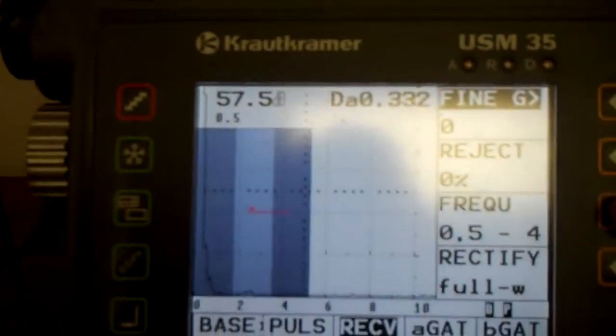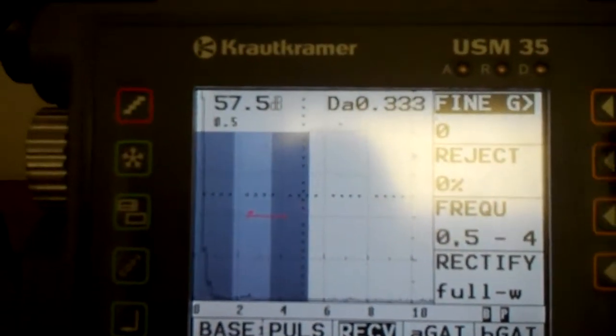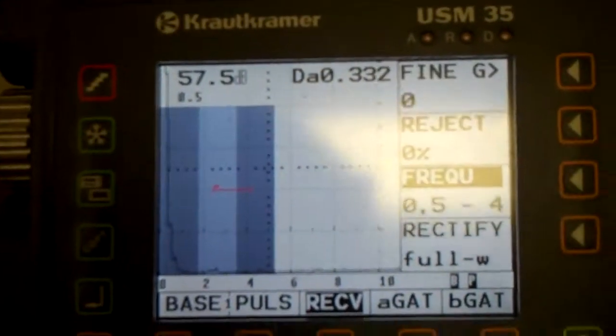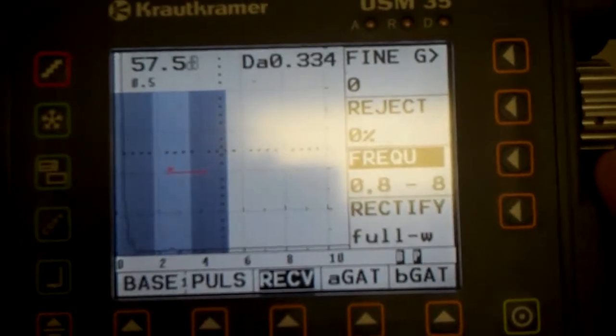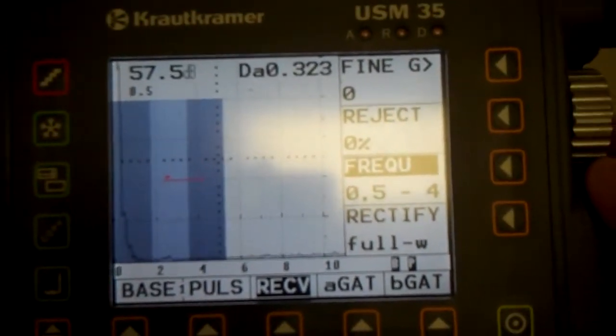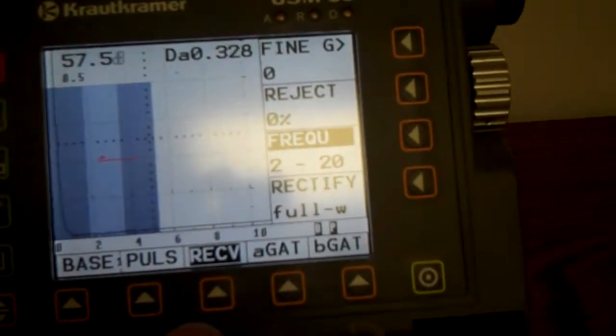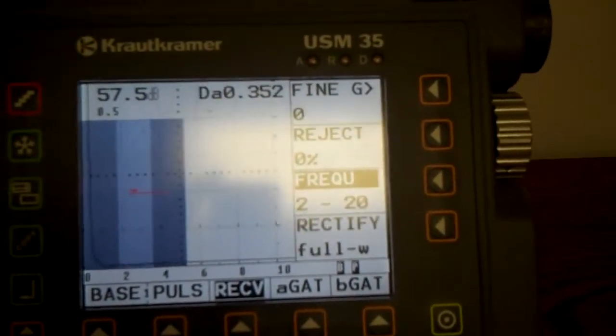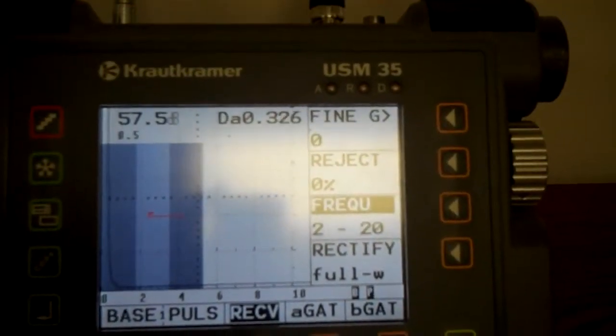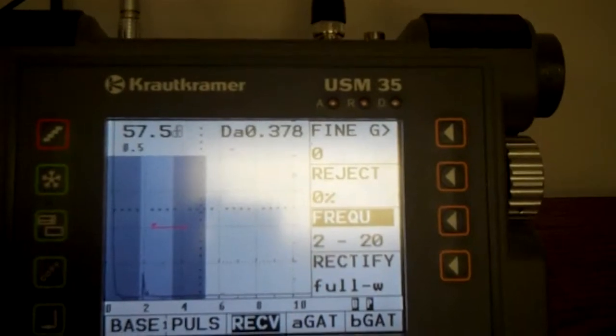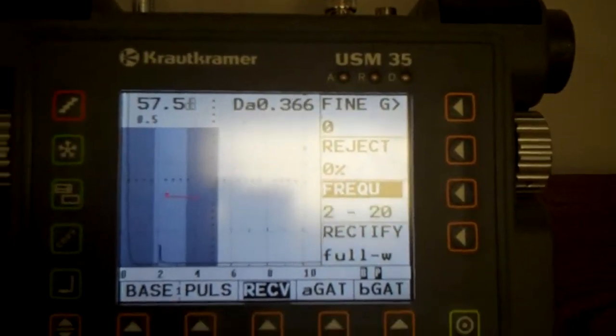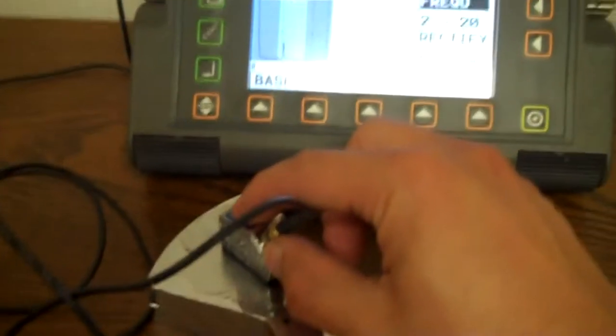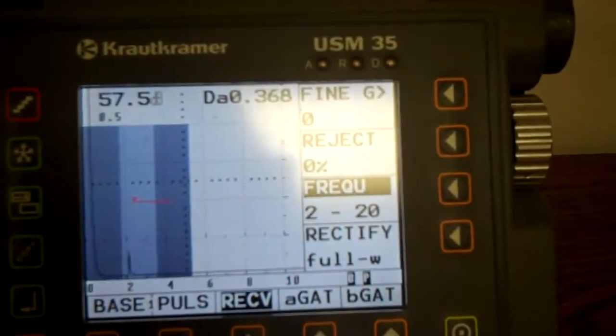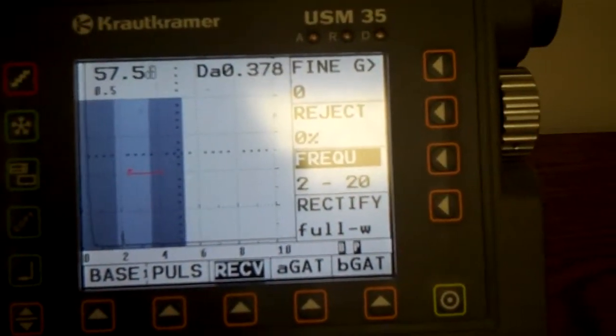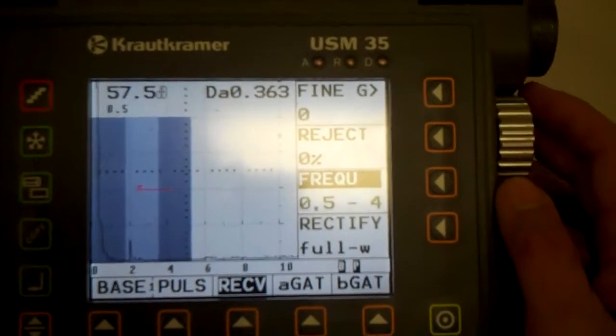Go to receiver. Okay? So we hit reject. We got rejected 0. That's good. Frequency 2 to 20, 0.5 to 4. We'll see what gives us the best screen resolution here. We just want to find something. There we go. And this is what I'm looking at. I just have my transducer on the block. I know that doesn't do anything for me yet. I'm just looking for signal clarity is all.